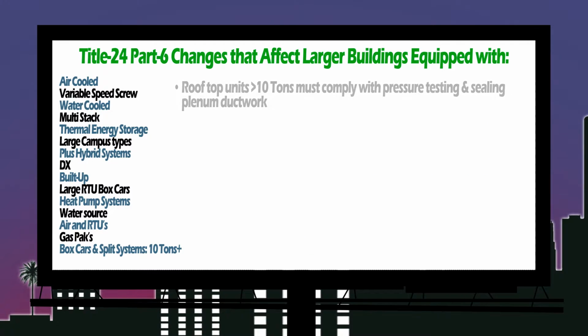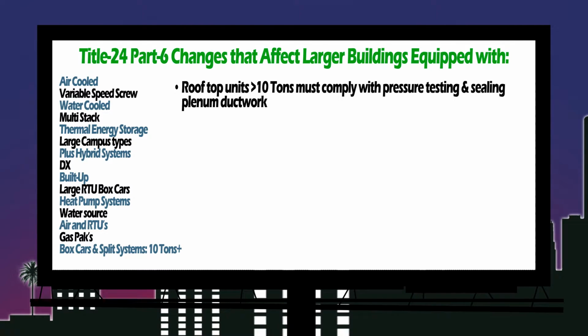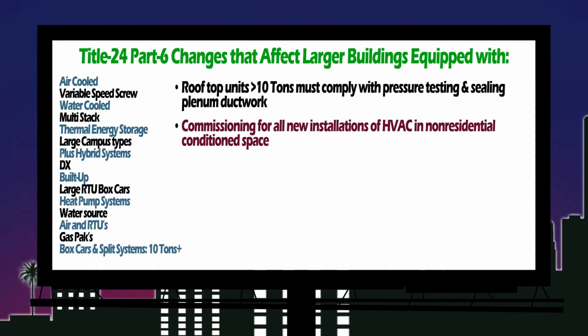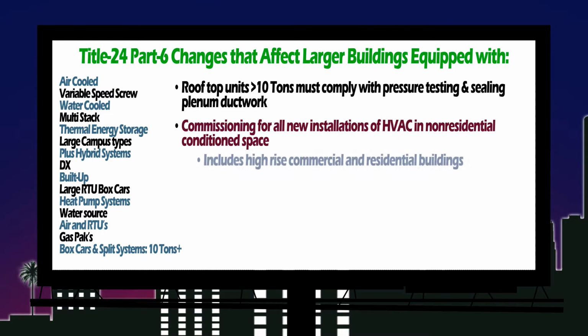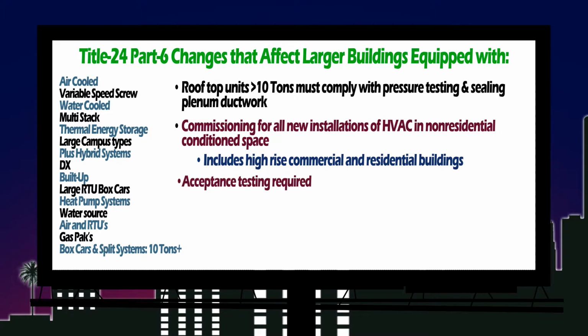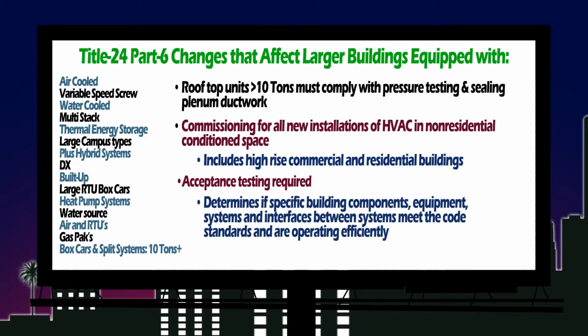In addition, rooftop units over 10 tons must comply with Title 24 requirements for pressure testing and sealing plenum ductwork. Plus, commissioning is now required for all new installations of HVAC in non-residential conditioned space. This includes high-rise commercial buildings and high-rise residential. And lastly, acceptance testing is required, which determines if specific building components, equipment, systems, and interfaces between systems meet the code standards and are operating efficiently.